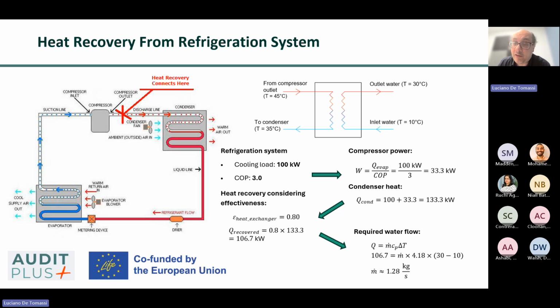However, the actual usable recovery is limited by heat exchanger effectiveness, which defines how closely the recovered heat approaches the maximum theoretical heat rejection. Typical effectiveness values range from about 50 to 85%, depending on design, fouling, temperature approach, and flow rates. The temperature of the recovered heat is primarily determined by the condensing temperature of the refrigeration system, which is itself a function of ambient conditions and system design. Since the condenser operates at a temperature higher than the desired heat sink, the recovered heat is usually available at medium temperature levels, typically in the range between 30 to 45 degrees Celsius for standard refrigeration and air conditioning systems, although higher temperatures may be achievable in some industrial systems.